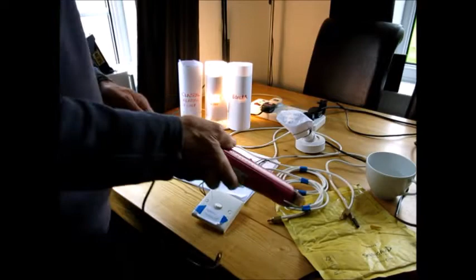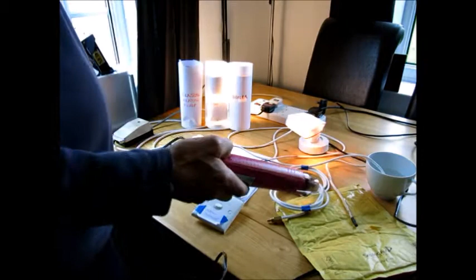While we're waiting for that to happen, I'm going to simulate, let me just check we can see. Yes, we can. Just come that way a little bit. I'm just going to simulate somebody turning on a hot tap by dipping the plate heat exchanger sensor, or the direct hot water sensor, into some cold water. And you'll see this is the heat exchanger pump light. So if I dip that in there, what will happen is this will start to come on.